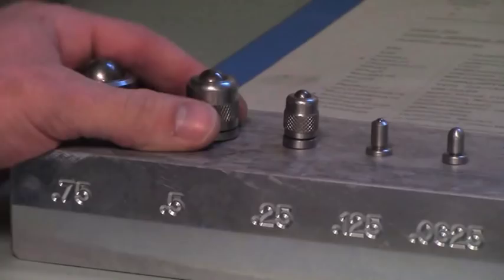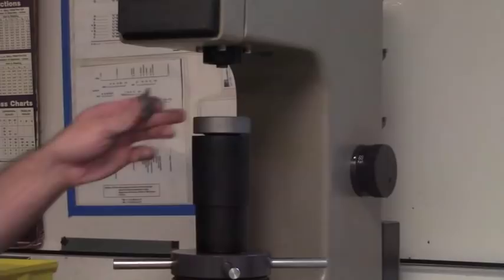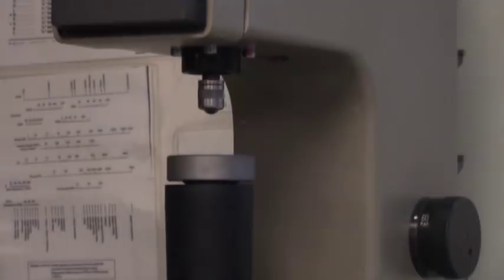Locate the correct indenter for the scale selected. We are using the R scale, which uses the half inch indenter. Simply place the indenter inside the machine and it will stay in place.